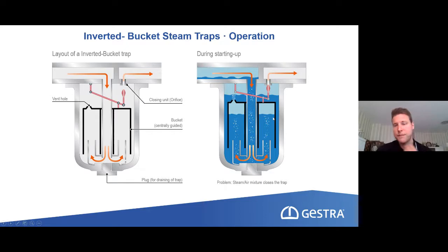So this is a good steam trap when it comes to the working principle, because we have no banking up of condensate, because it's a float principle we have here. But we have the disadvantages of closing in the steam area and the problem with the air venting.